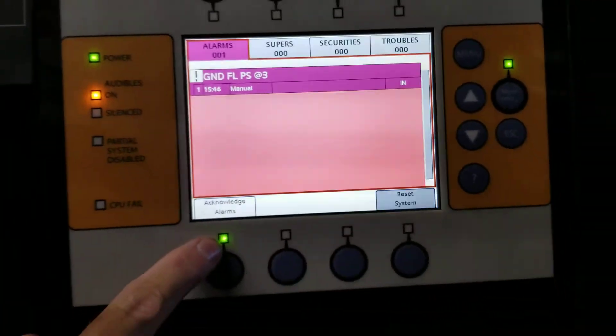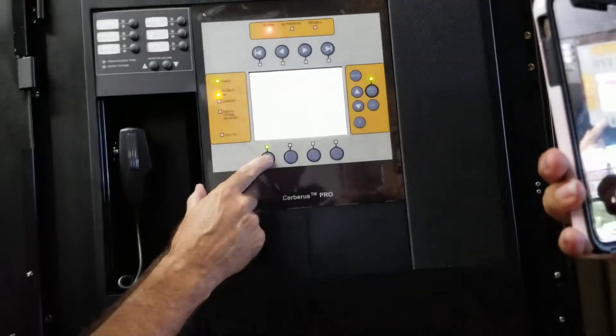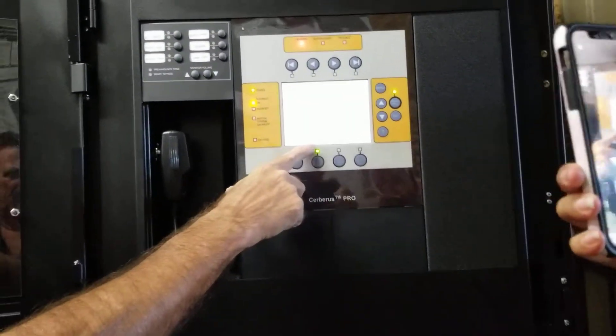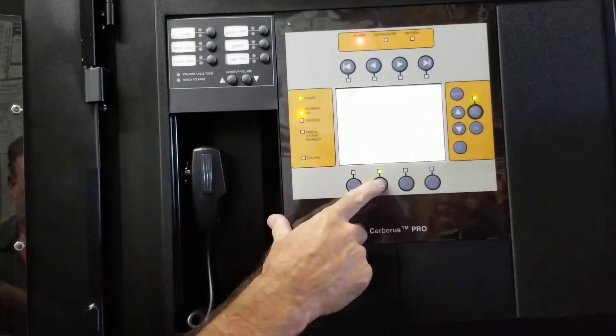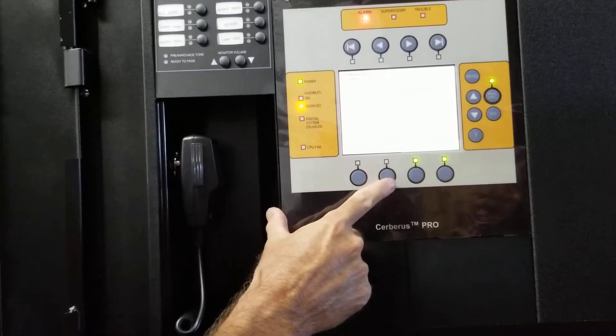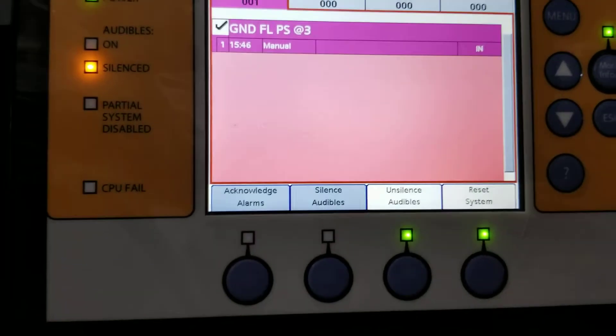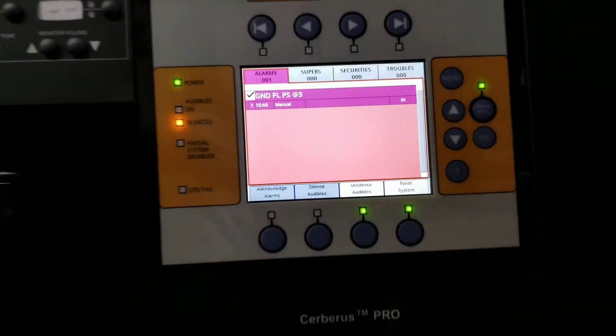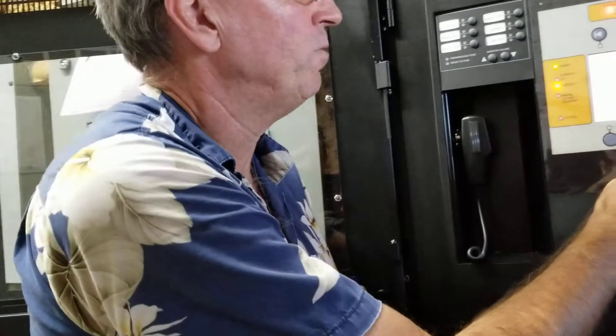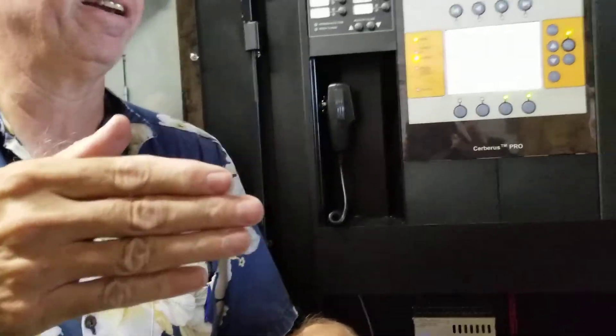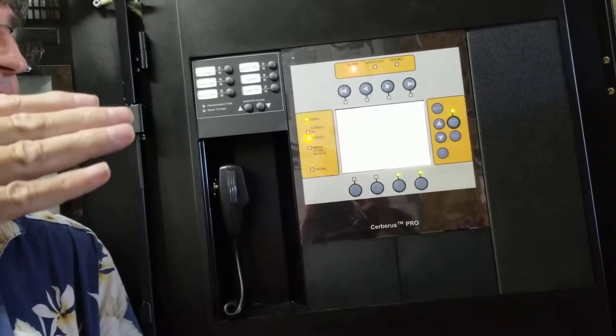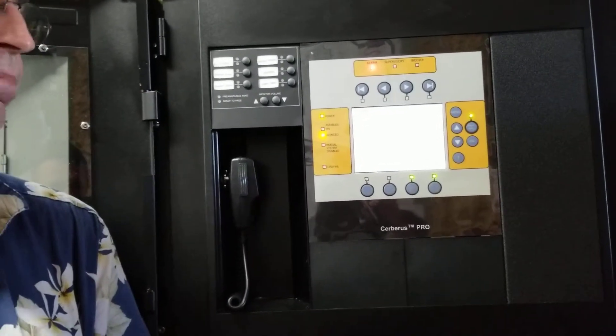First thing you have to hit — it's highlighted — acknowledge alarm. Then the only button that shows that you can hit is silence alarm, which will silence it. Before we reset the system, I just want to go over what I did at the pull station. I pulled the pull station, then I opened up the door, and that allowed that pull station to reset. If I didn't open the door and allow that pull station to reset, if I had reset the system, the system would try to reset and then the fire alarm is going to go right off again because the pull station is still in alarm status.